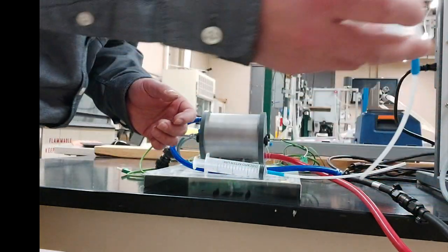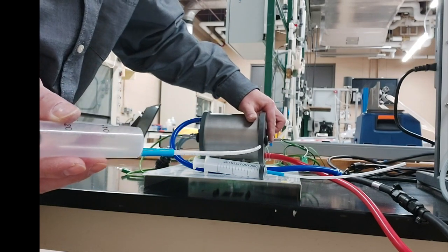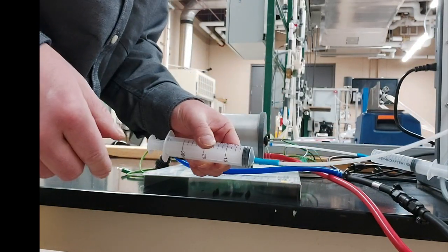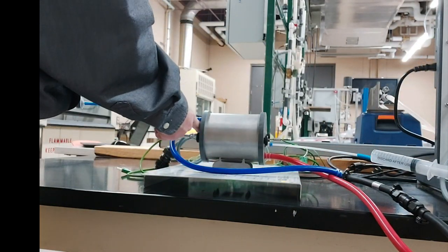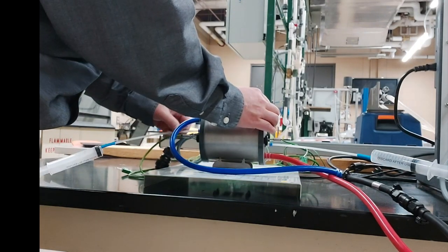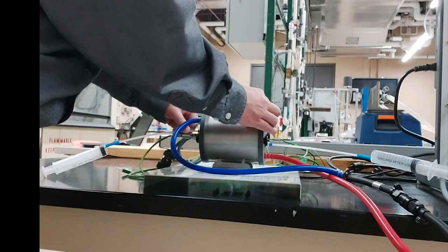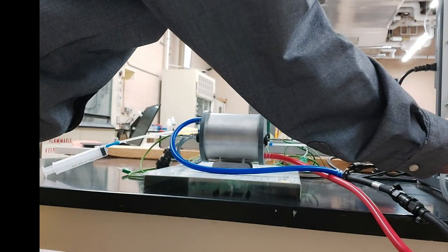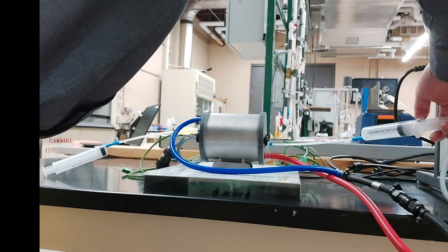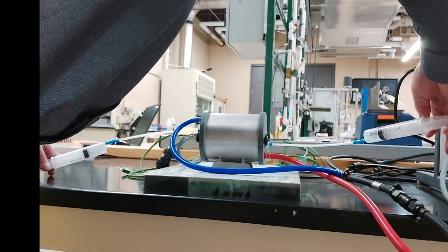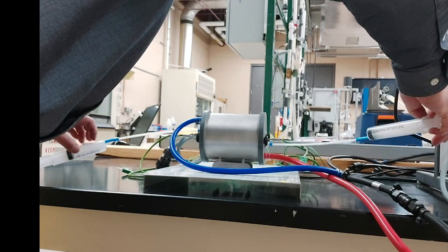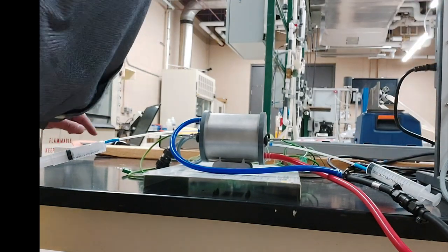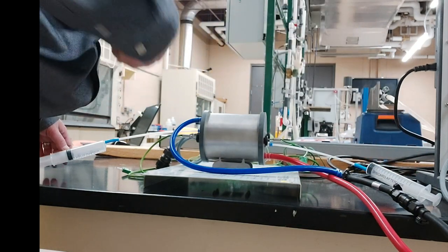Then connect the plastic tube of the syringe filled with air to the blue quick connector on the gas cylinder. Hold the plastic tube and push it in until it stops. Connect the plastic tube of the other syringe to the blue quick connector on the other side of the gas cylinder in the same manner. Now you will push the plunger of the syringe that is filled with air and confirm that the air goes out of the cylinder from the other side into the second syringe. This means that air went through the cylinder from the inlet to the outlet.